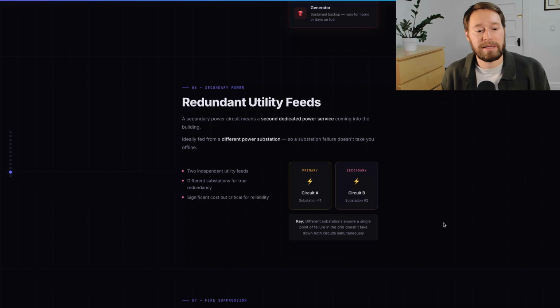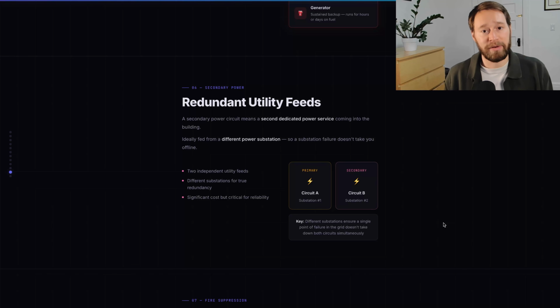Secondary power is literally just another utility coming into the building. Data centers do this where they get one utility from one substation as the primary power, and another utility of the same size from a different substation, so that if an entire part of the grid goes down, like an entire substation going offline, they have another power source coming from somewhere else. This acts as an intermediary failover before generators kick on.